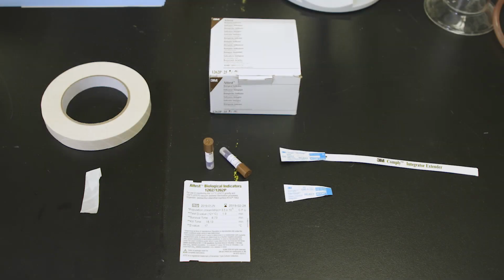Although autoclave tape and other chemical indicators are easy to use, these tools only indicate that your items have reached 121 degrees Celsius at some point during the run. They do not necessarily indicate that your load has been sterilized.